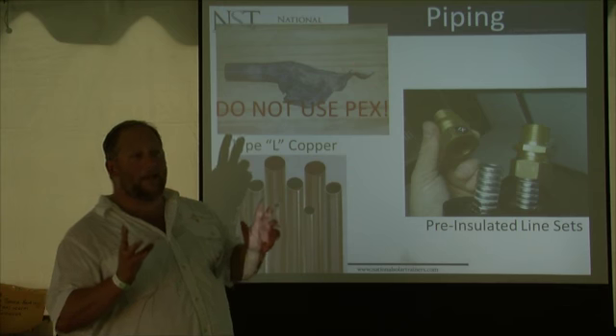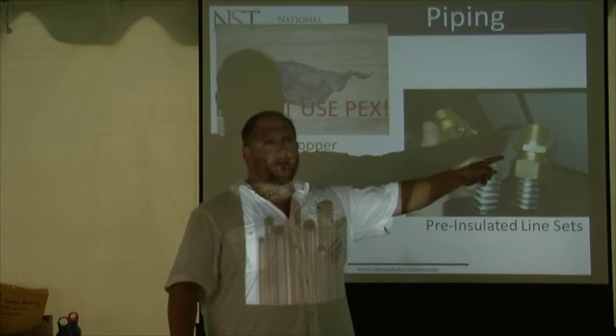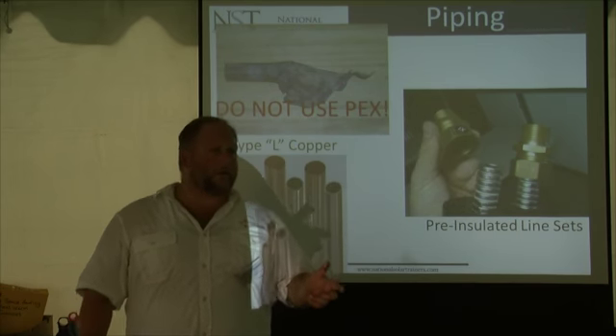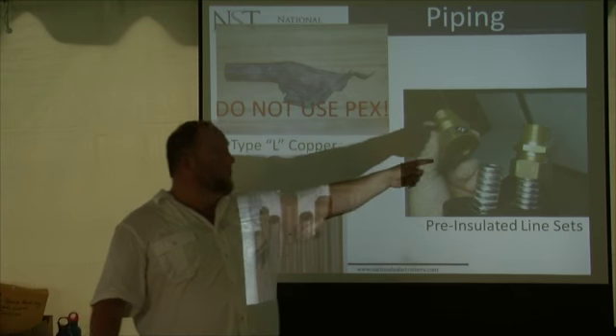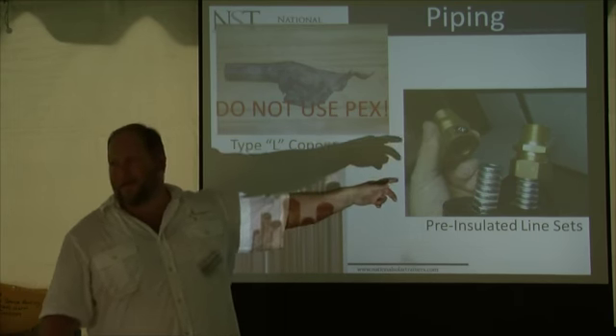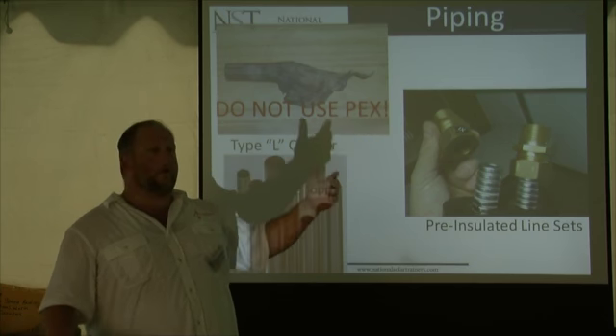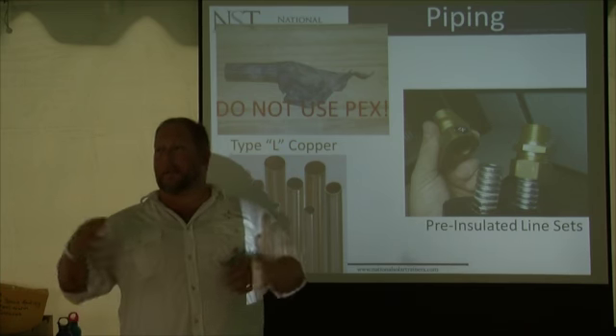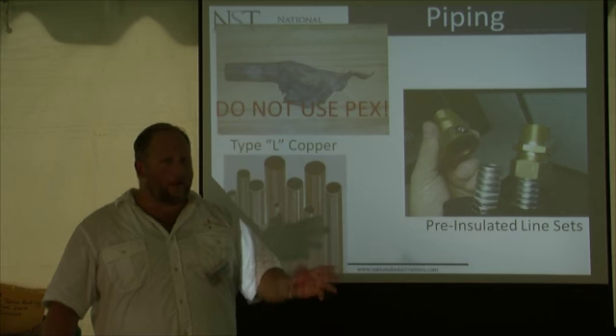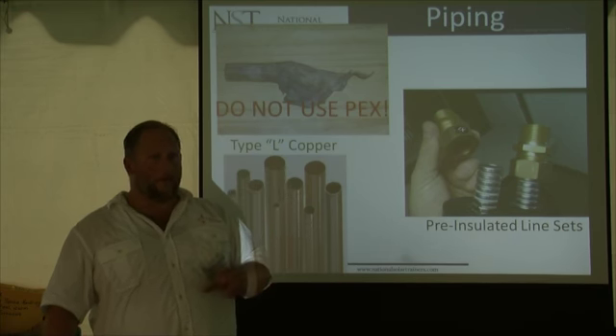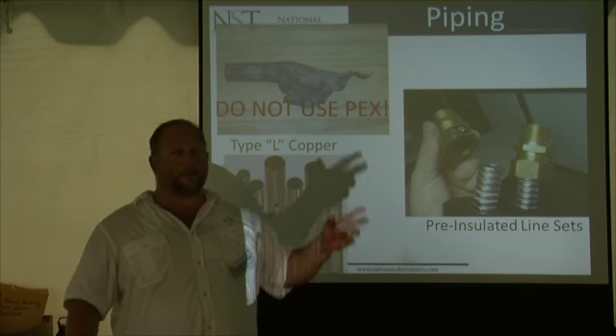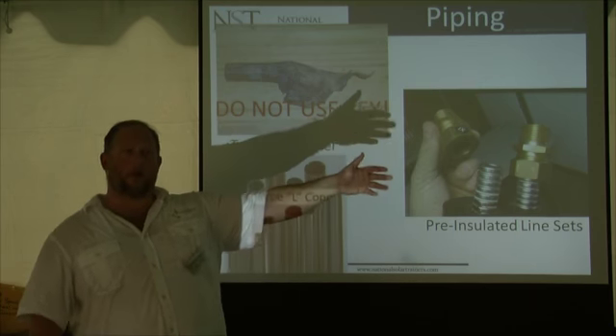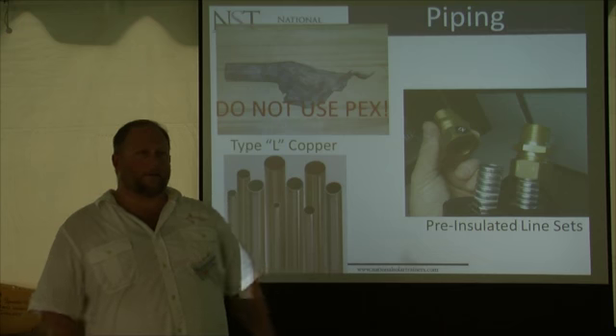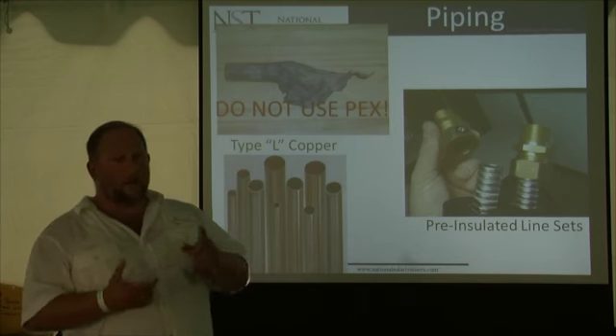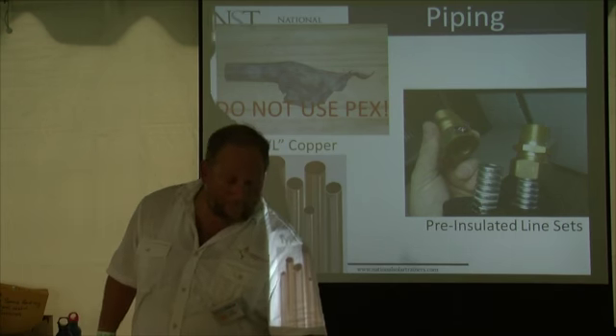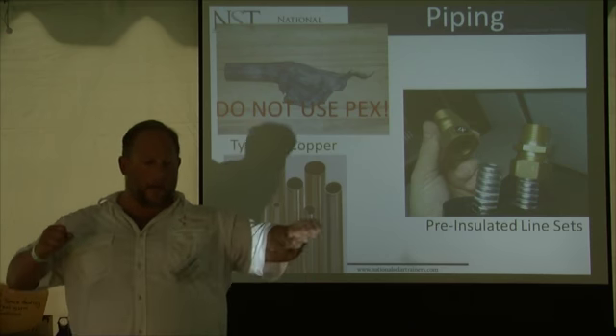But be careful, because they sell line set and they also sell the connections, these brass connections. $11 a linear foot for line set isn't so bad, but every one of these connectors is $15, and how many do you need - 8, 16? So make sure, since you'll find people selling lots of different types of line set, you check how much the connectors are and how readily available they are. Do they only have 5 in stock and discontinued them? Because then you'll never find another one to fit. You can't just go to the hardware store and get these connected, they're called quick connects. So you have to understand the cost with the connections, and how flexible it is - you could tie it in a knot.